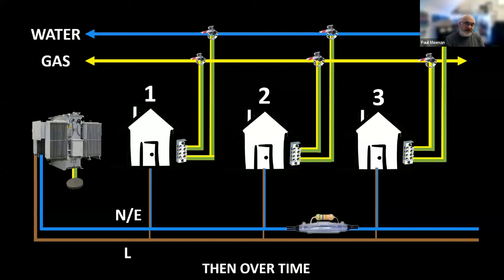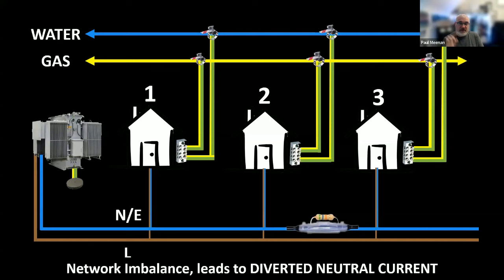And then after 50 years, 70 years, these cables will get old, they'll be jointed, the joints may not be good, and like with any loose connection, loose wires start fires. Now, over time, the impedance or resistance of your cable can go high. And what will happen is that neutral, say from house three, the return current, when it tries to go back to the substation, will meet a high resistance. So it won't want to go there. And this leads to a network imbalance, because what's going out is not coming back. So what we find is that when you put a clamp meter on your earth wire, that water, which is a lead pipe or an old copper pipe in the ground, some of the energy will divert into those lead and copper pipes, and may travel all the way through and divert around the high resistance joint and into house number two. So number three can be fed via the gas or water main into number two. So that's known as diverted neutral current or neutral current diversion.